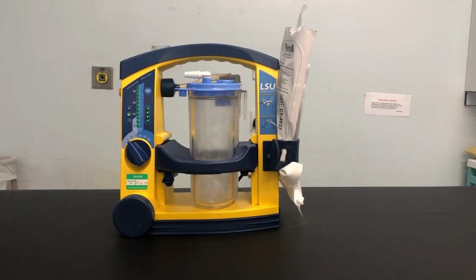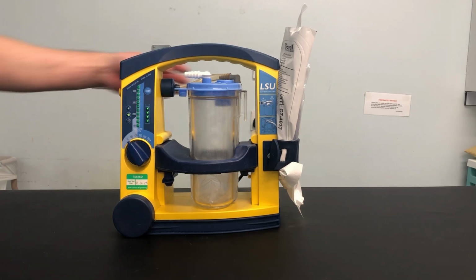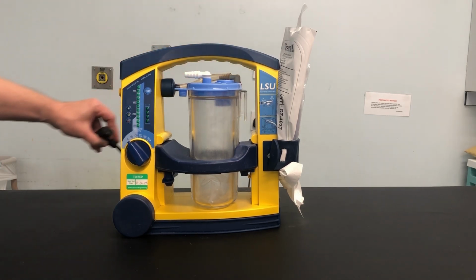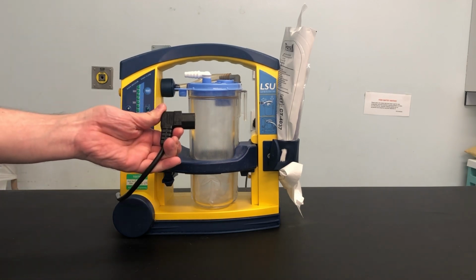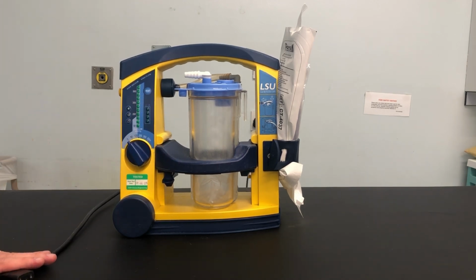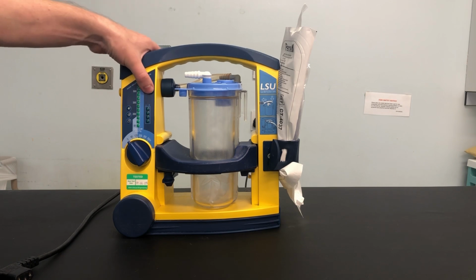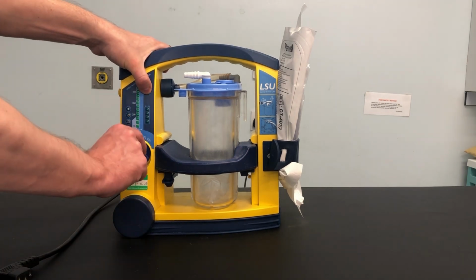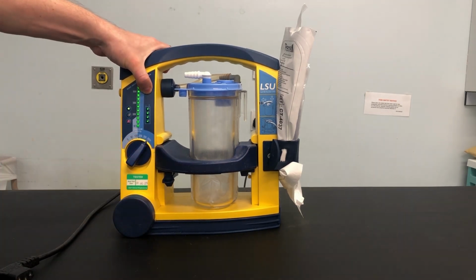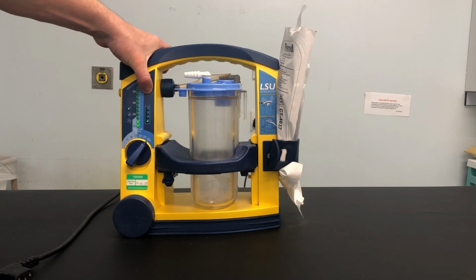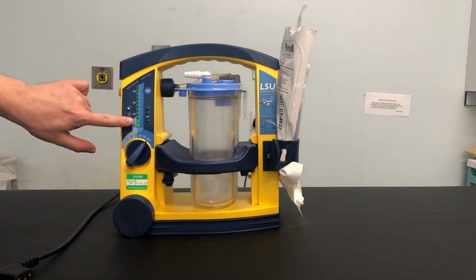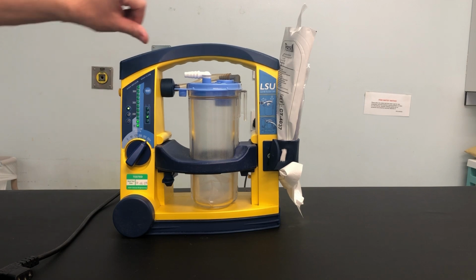So performing the daily test. Before the test can be performed, again, make sure that this device is disconnected from the mains power and that all the connections are secure. Press and hold the test button while setting the operating knob to 500 millimeters of mercury. Do not release the test button until 2 seconds after the operating knob has been set to 500 millimeters of mercury.